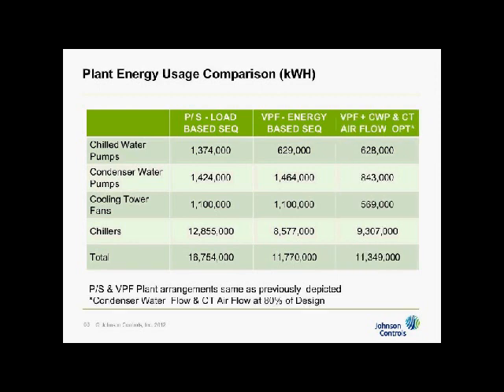Last, we tried to answer this question for this myth. What happens when we reduce the condenser water pump flow or the cooling tower airflow with variable speed drives? As I said before, we ended up at 80% of design flow, and now you can see the savings. The chill water pump, of course, remained at the same savings as the previous column, but now the condenser water pump energy went from 1.5 million down to 843,000 kilowatt hours in 1 year. The cooling tower fans energy was reduced from 1.1 million to 569,000 kilowatt hours per year.